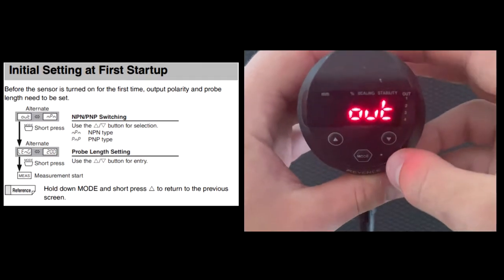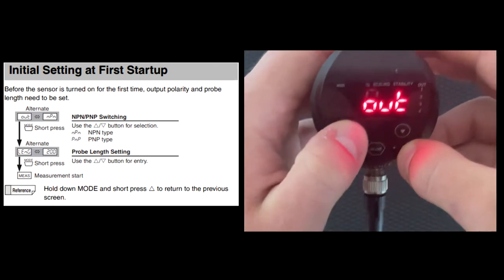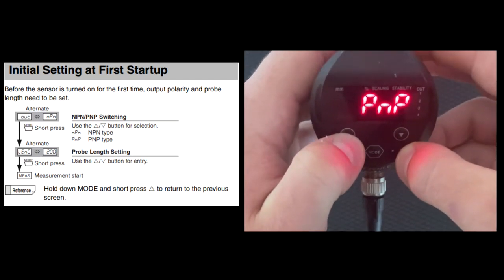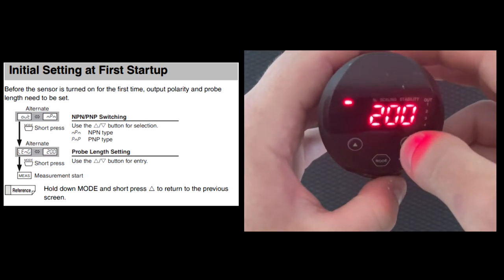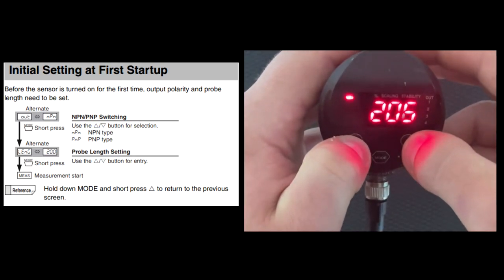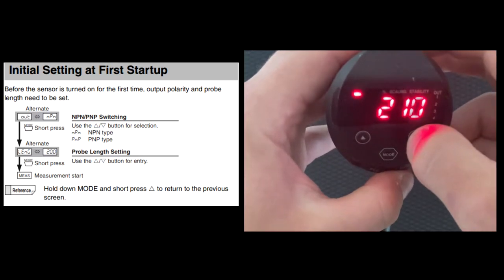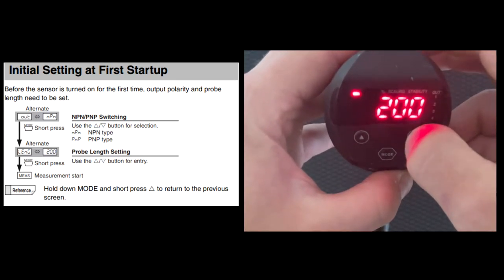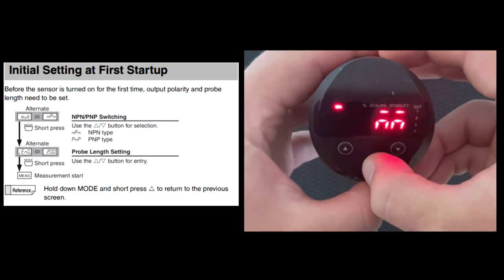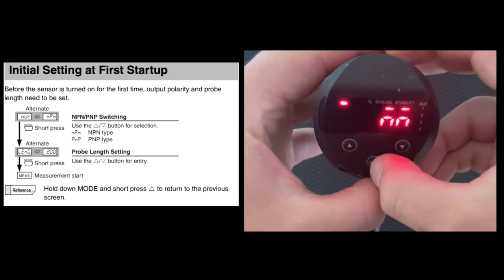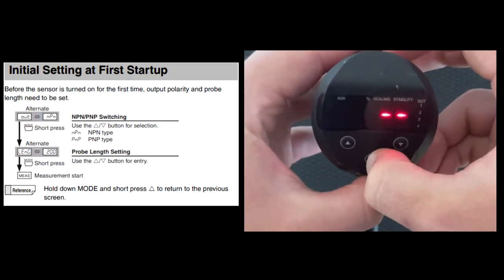When you first give power to the FL level sensor, you'll be greeted with the initial settings menu. Here you can select whether you need NPN or PNP and set the probe length designated by either the part number that you have received or if you had cut the probe within at least plus or minus 5 millimeters of the actual length. Finally, you can set your units as either percent or millimeters of the probe in the liquid.